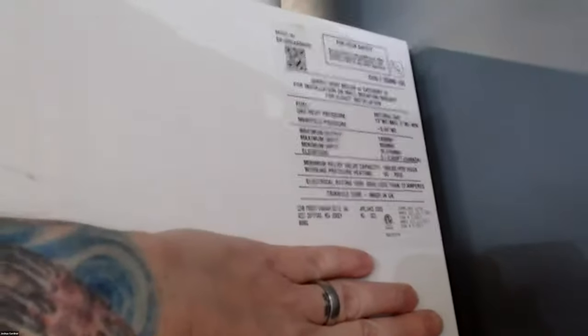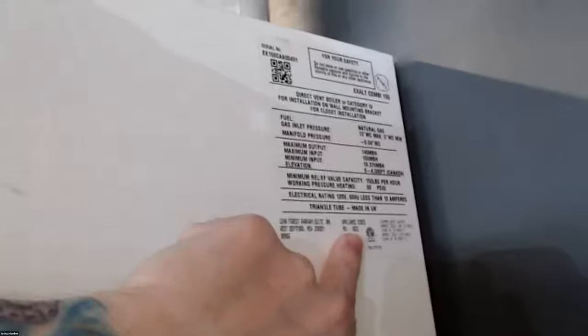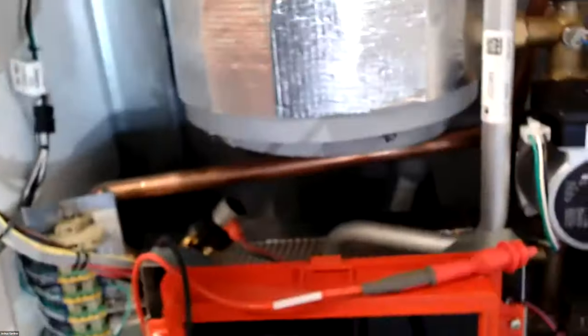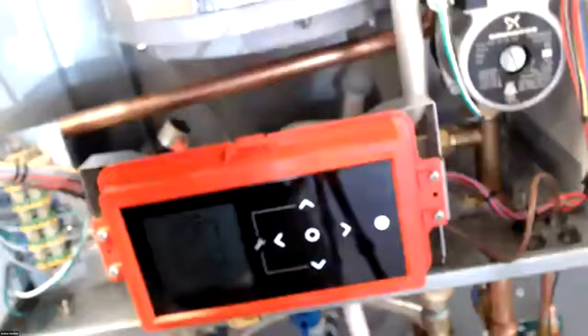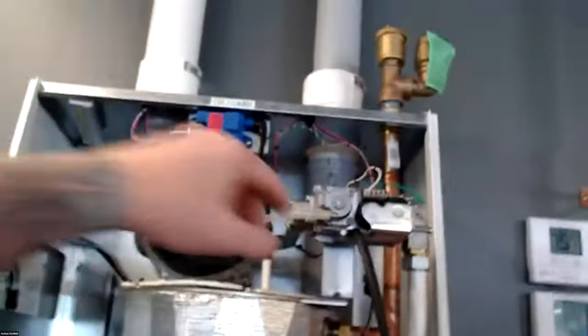So if you're converting, you'll take the new propane sticker and put it right over this one. That way we know it's converted. And then you'll look at the LP code and the appliance code, and you'll enter it in here on the control. And that's the only single change on the unit. So that is basically all you'll do for the conversion. It's pretty simple, not too much to it. And then you'll go through and you'll set up your combustion, okay?